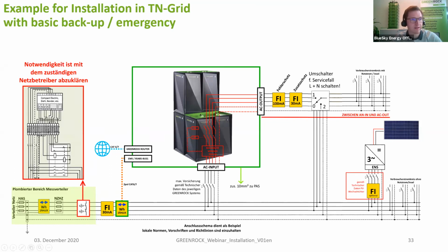What you can also already see here is the backup connection. So inside the system, there is an AC in connection and an AC out connection. AC in is a bidirectional charge and discharge connection point, but also the AC out is. But the thing is, as soon as you have a grid loss or a grid failure, the system will actively disconnect from the grid, which you can see here with these red power switches, but the AC out stays active or gets active again within 20 milliseconds. So if you have loads connected to this connection, they will stay active.